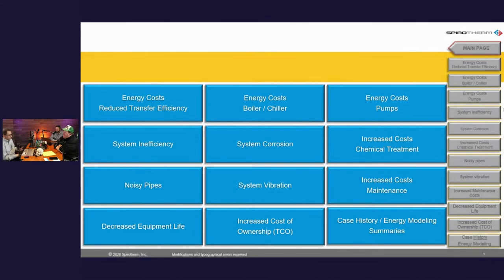Something we discovered by mistake: air is an insulator. We started getting feedback from clients saying their system wasn't having to run as long, getting better heat transfer, more delta T at the coil. And the answer was: we just removed the air. I always point to double or triple pane windows — there's a gas in there slowing the heat transfer. Same thing's happening inside our pipes. We insulate the exterior of the pipes, but nobody thinks about the bubbles circulating through the inside. The system still works — it's just having to run longer. So we're wasting energy.